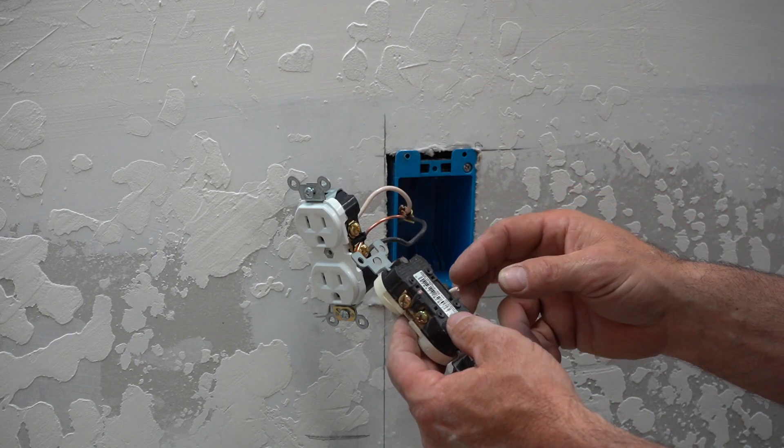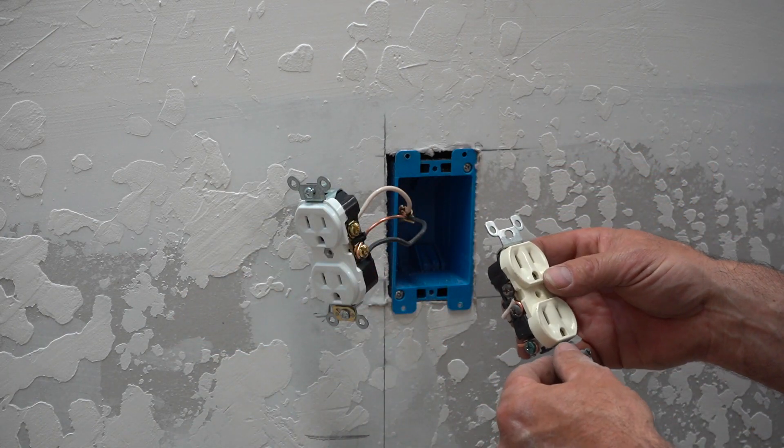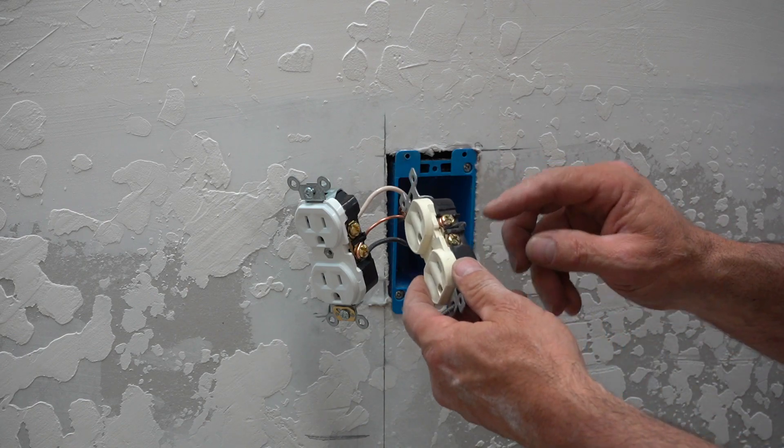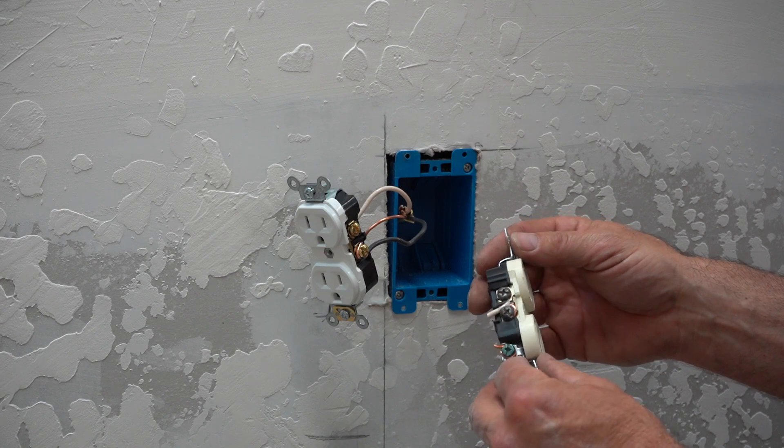But when you use these they corrode, sometimes they don't seat in all the way, sometimes you'll get a failure. It may be later on after you have everything finished and then you got to go try to find out which one it is in the run. So use the screws, use the screws, use the screws. That's the best bet and they'll hold the best and get the best connection.